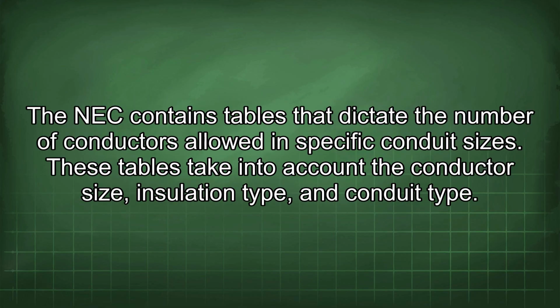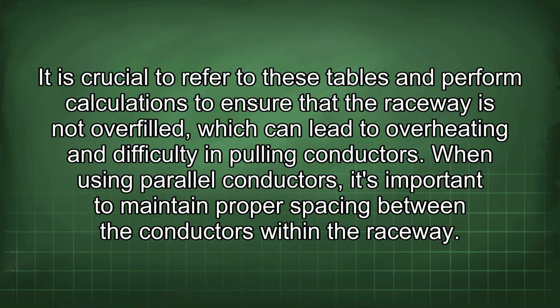The NEC contains tables that dictate the number of conductors allowed in specific conduit sizes. These tables take into account the conductor size, insulation type, and conduit type. It is crucial to refer to these tables and perform calculations to ensure that the raceway is not overfilled, which can lead to overheating and difficulty in pulling conductors.